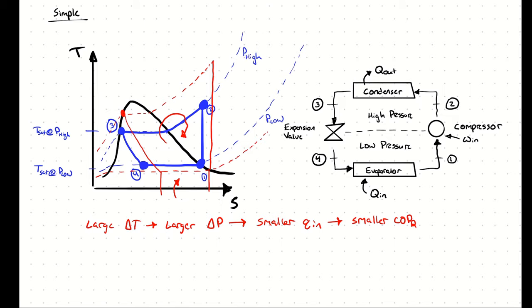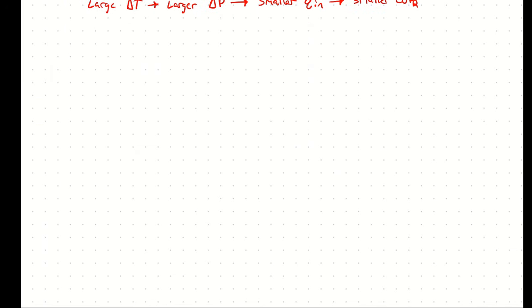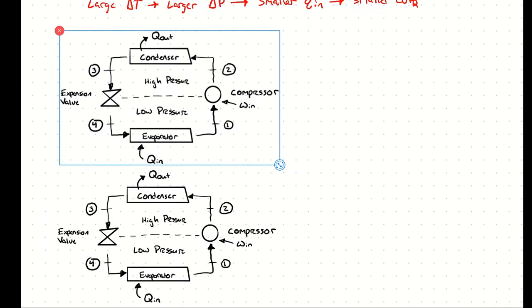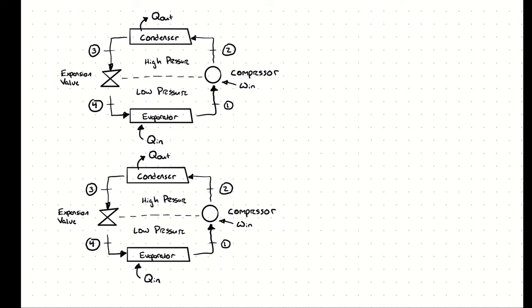One solution to that problem is to split the refrigeration cycle across multiple refrigeration stages — literally putting refrigeration cycles end to end, where the heat pushed out from one condenser is pulled in to the next evaporator. This is referred to as multi-stage refrigeration, sometimes called cascade refrigeration. In very low temperature refrigeration cycles, you might even need three or four stages. They may have different operating pressures and different working fluids, but the principle is the same across each of them.